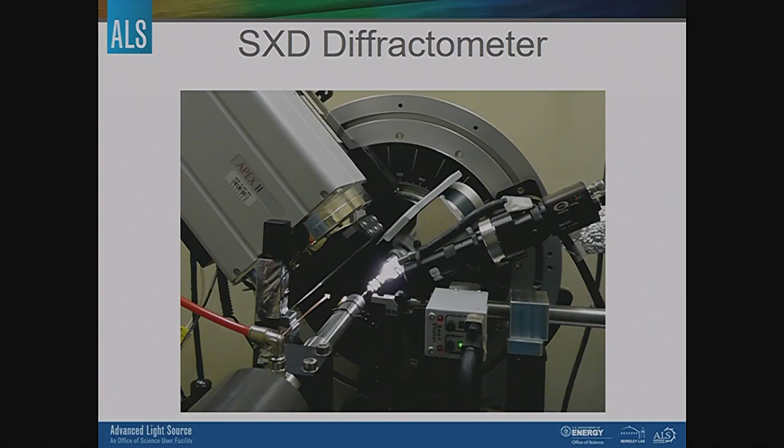I'm not going to say any brands are better than others, but this is a very typical single crystal diffractometer, except this one is at a synchrotron, so it is on its side due to the polarization of the beam. You would usually have it sitting on the base, which is behind here in a lab source, because the polarization is different. So here's our 2 theta angle. Here's the detector. That is omega right there. And that block right here is the phi block, and the phi rotation occurs at the end of that block.